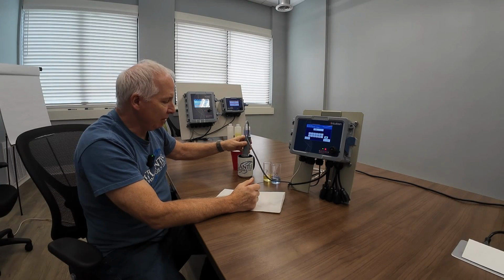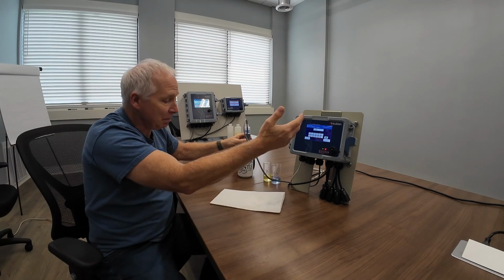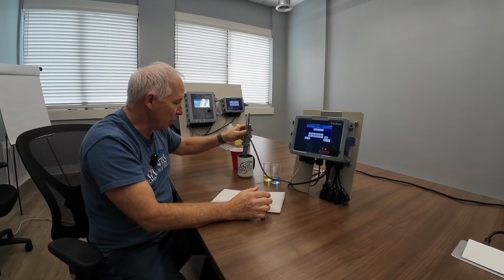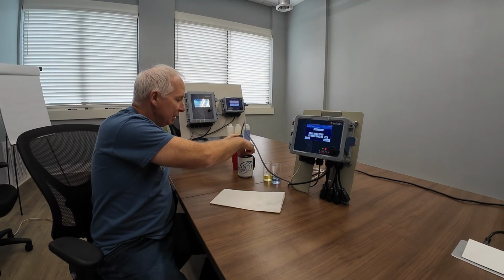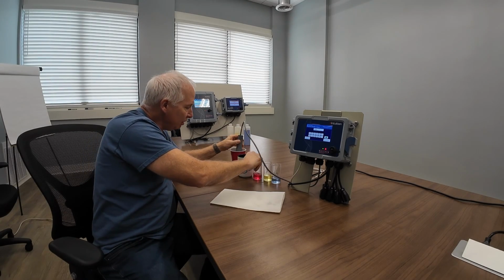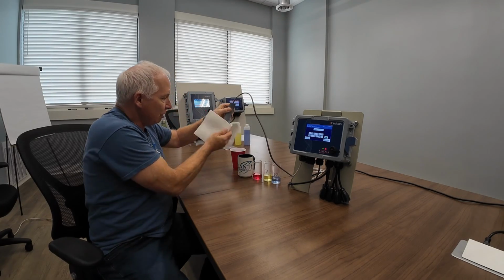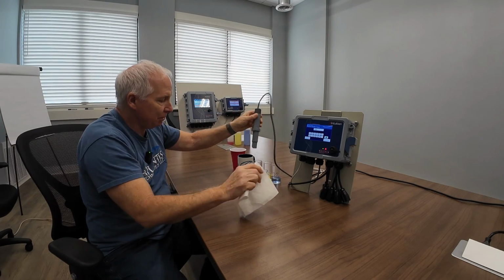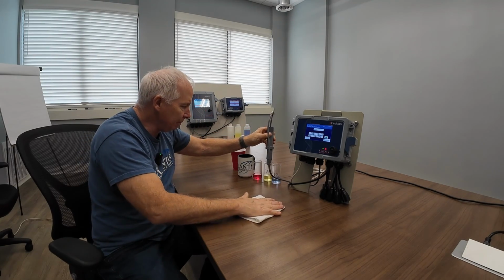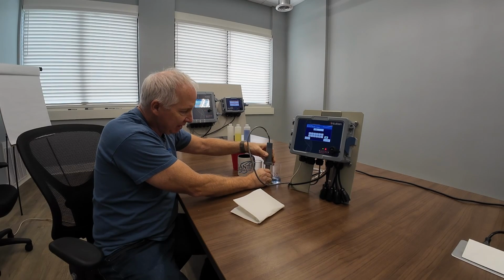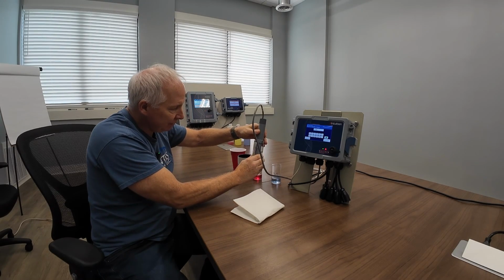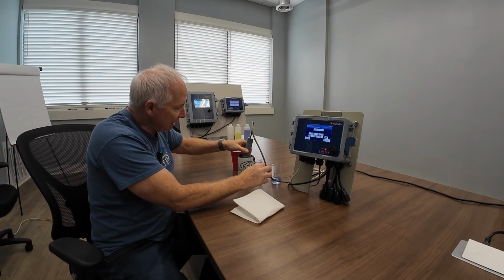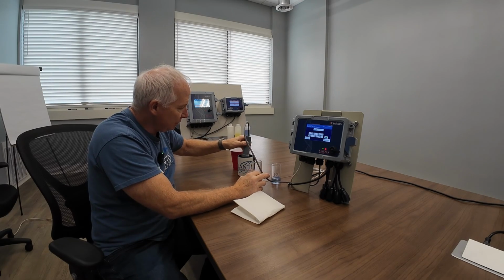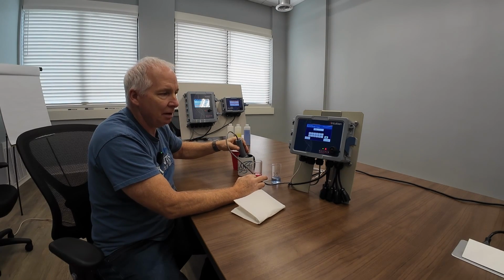Now I normally go just 4, 7, and 10. It may tell you something else, but we're going to do 4, 7, and 10. So I'm going to clean the sensor off and dry the water off so I'm not contaminating my next buffer. I'm going to put it in the 7 and let that sit here. We're going to have a time delay right now because we've got to wait a minute or so for this to stabilize.